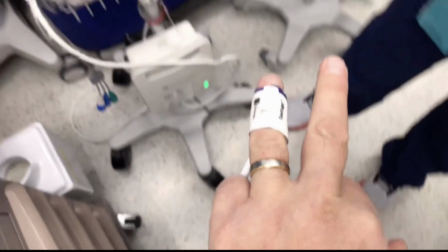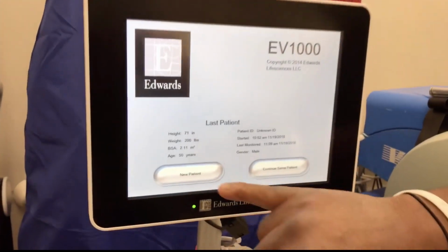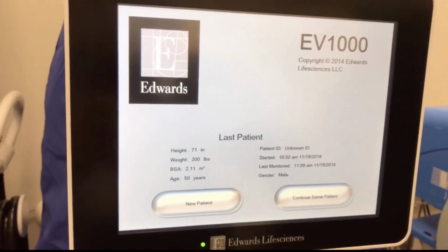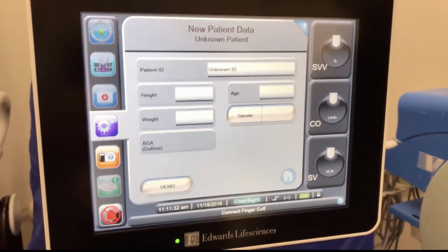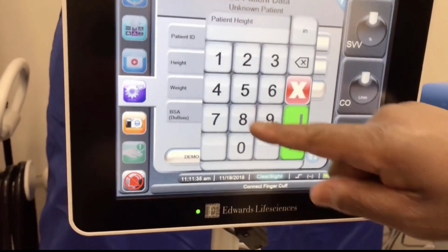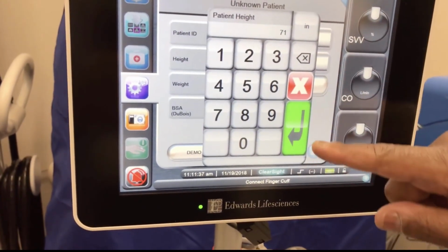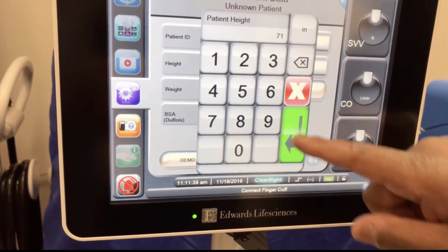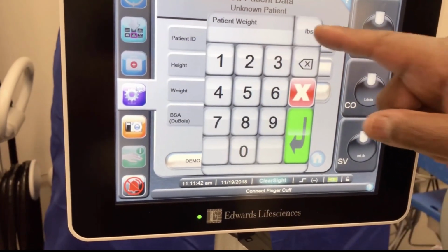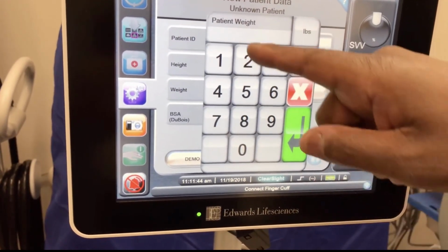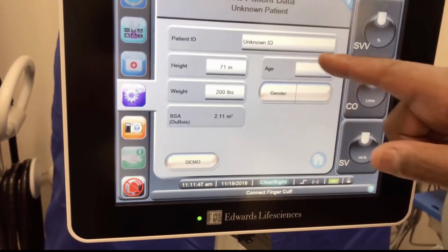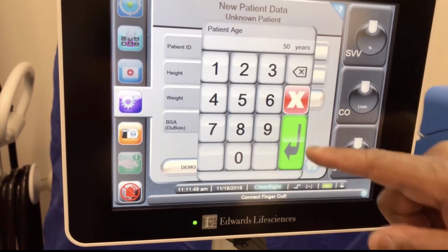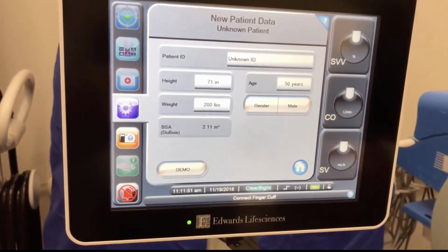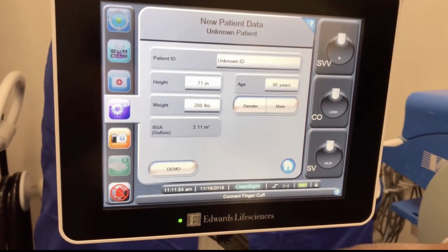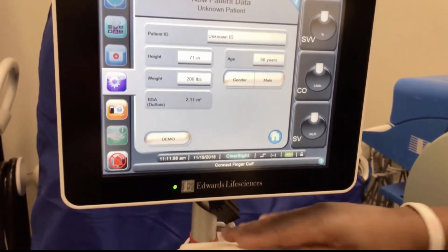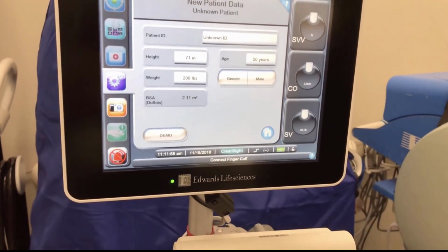The next thing is we always want to start with a new patient. We're going to hit new patient. At this point, it is going to ask you for the patient's BSA. The height, 71 inches, and you can do inches or centimeters. We've chosen inches. We're going to do weight, which can be done in pounds or kilograms. We're going to do pounds, 200 pounds. We're going to do age and gender. This is all important for the BSA, and this is going to compute the numbers that it compares to in your data box here. So at that point, you're done.